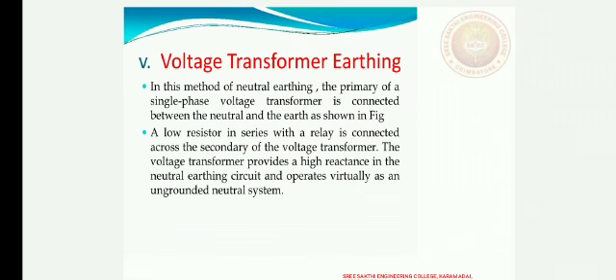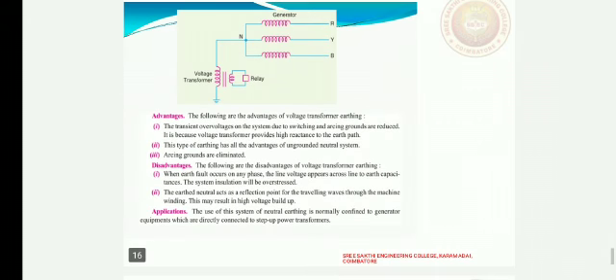And fifth one, voltage transformer earthing. In this system of earthing, the neutral point is earthed through a single phase voltage transformer. The system thus acts as an insulated neutral system. A very high reactance earthing is provided due to the voltage transformer. The voltage transformer shown in the figure measures the voltage so that an earth fault on the system is indicated. The traveling waves passing through the machine winding are reflected through the voltage transformer. A surge diverter is used between neutral and earth to avoid the rise of voltage. This is necessary in systems with operating voltages between 2.2 kV and 3.3 kV.